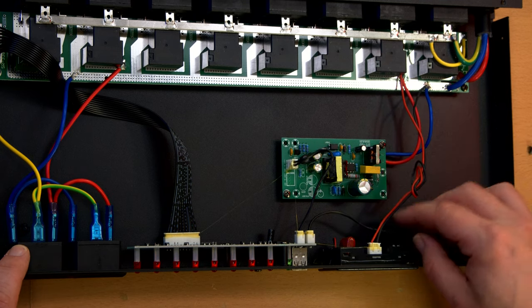So let's just see how does this come off? Now they actually made a reasonable attempt at making this connection solid. I was worried that they were just going to take the bare copper wire or aluminum wire from this cable and just try to screw it onto these terminals. And with 10 gauge wire that would not work very well. But I'm glad to see they actually crimped on connectors.